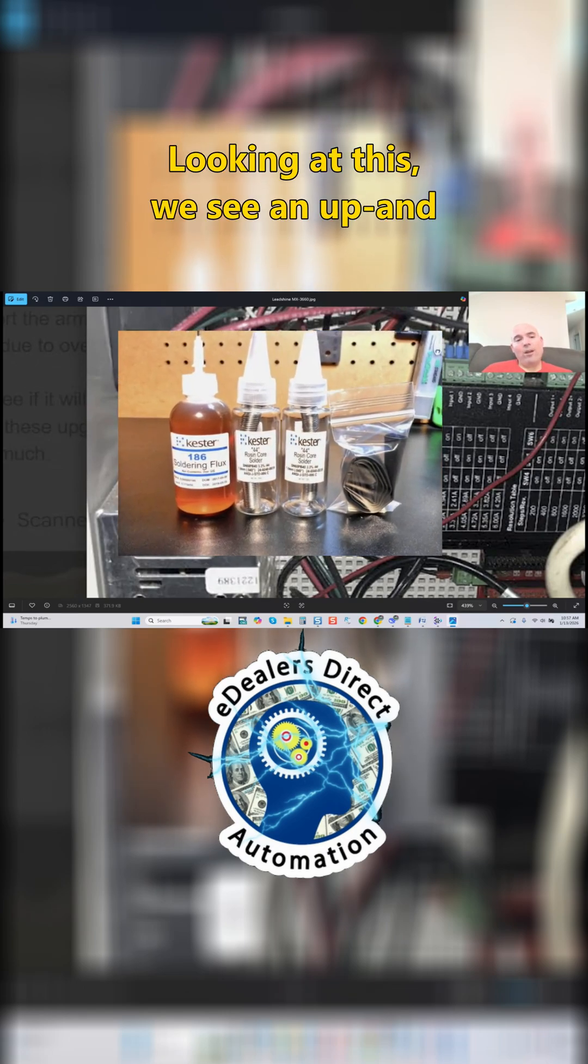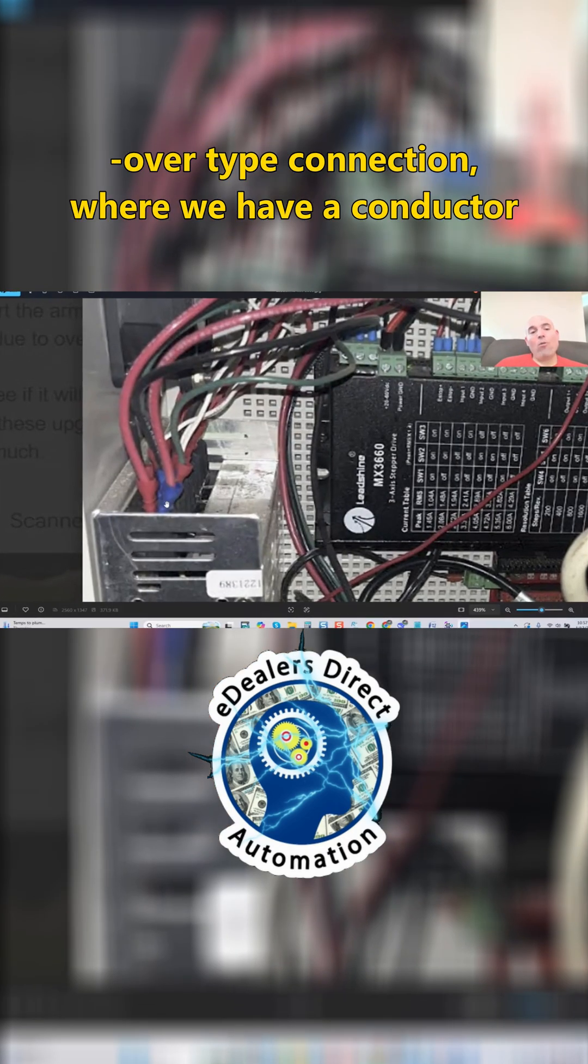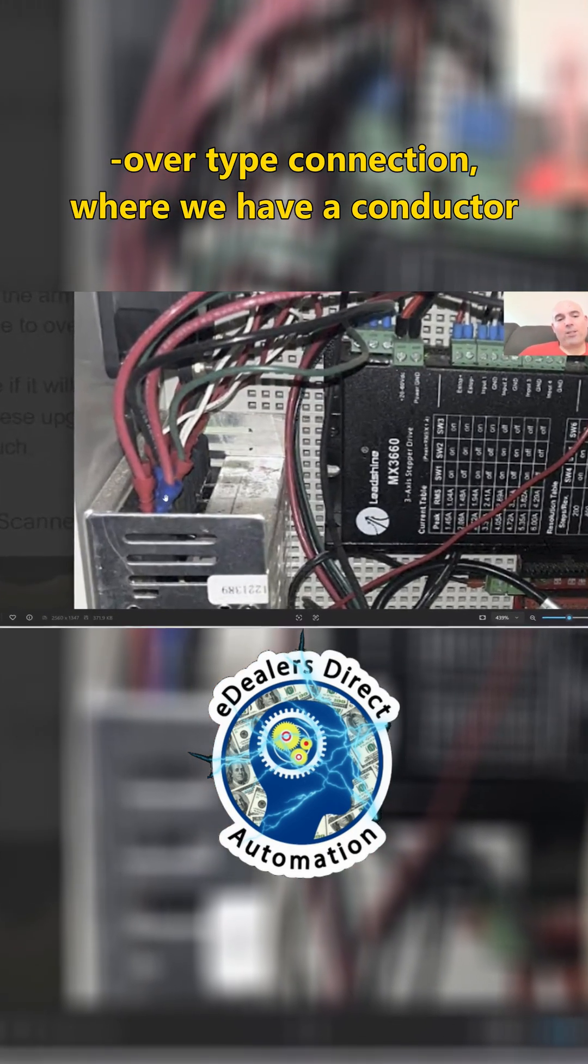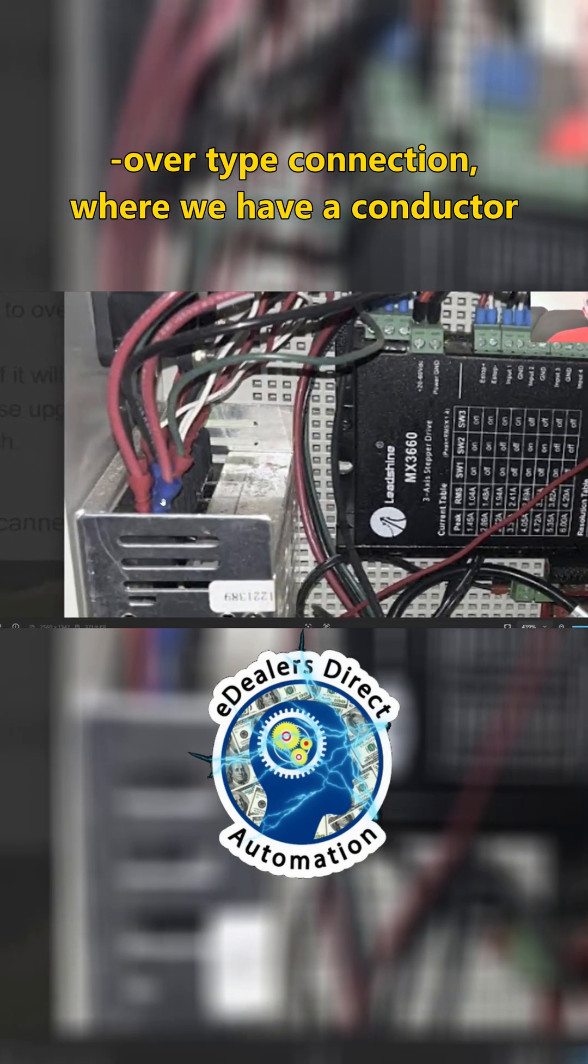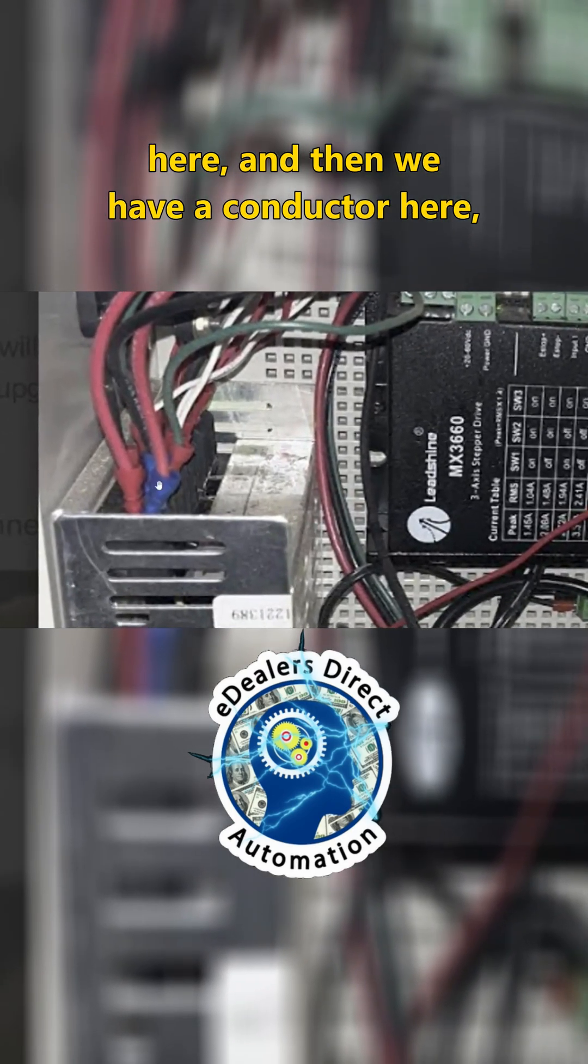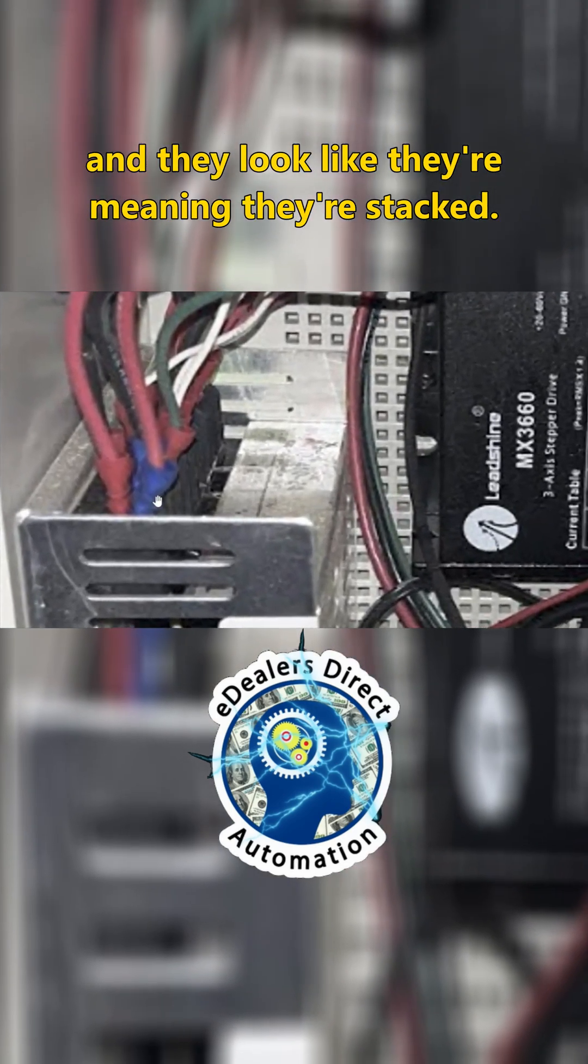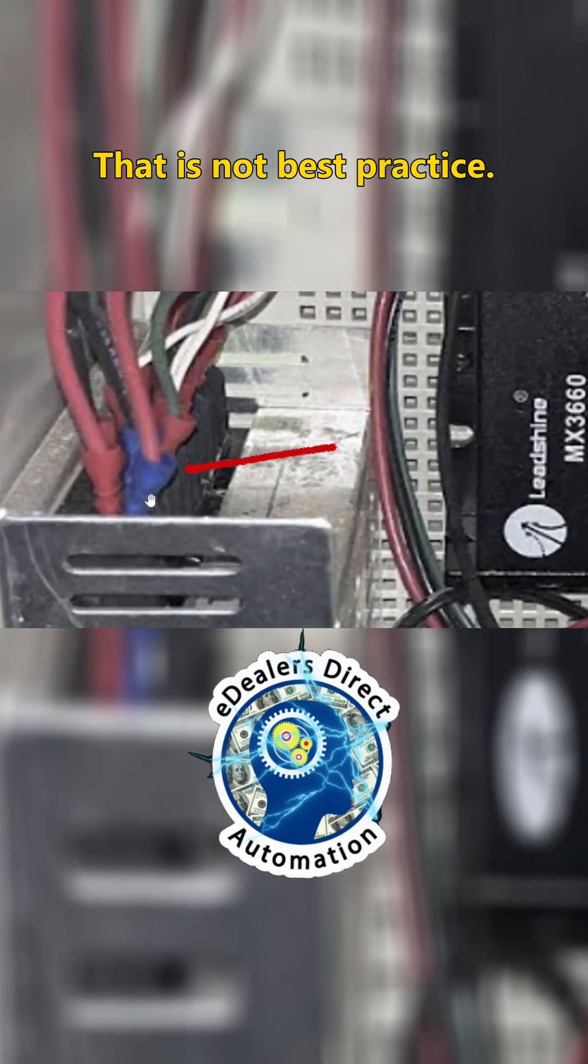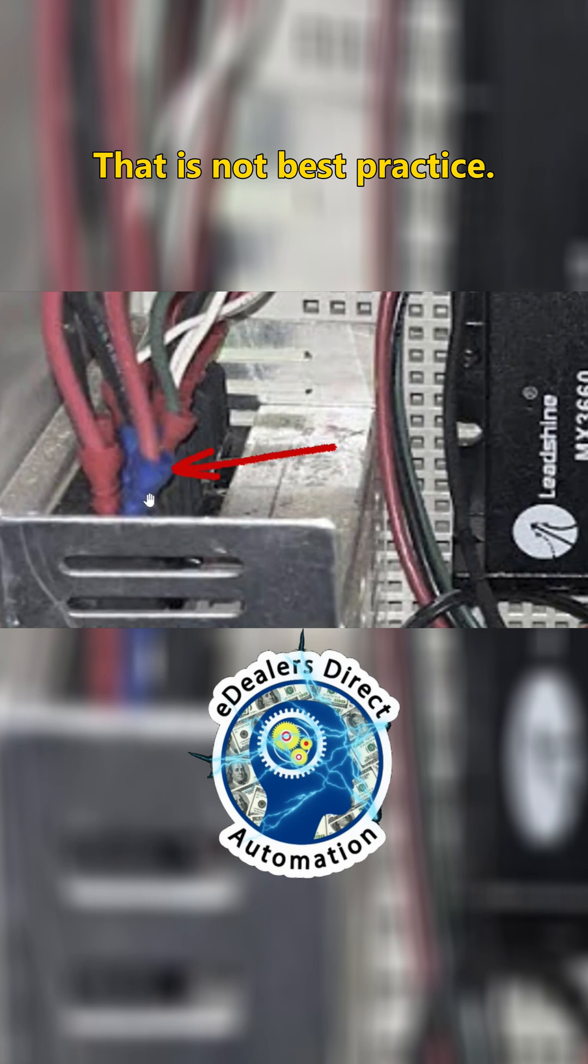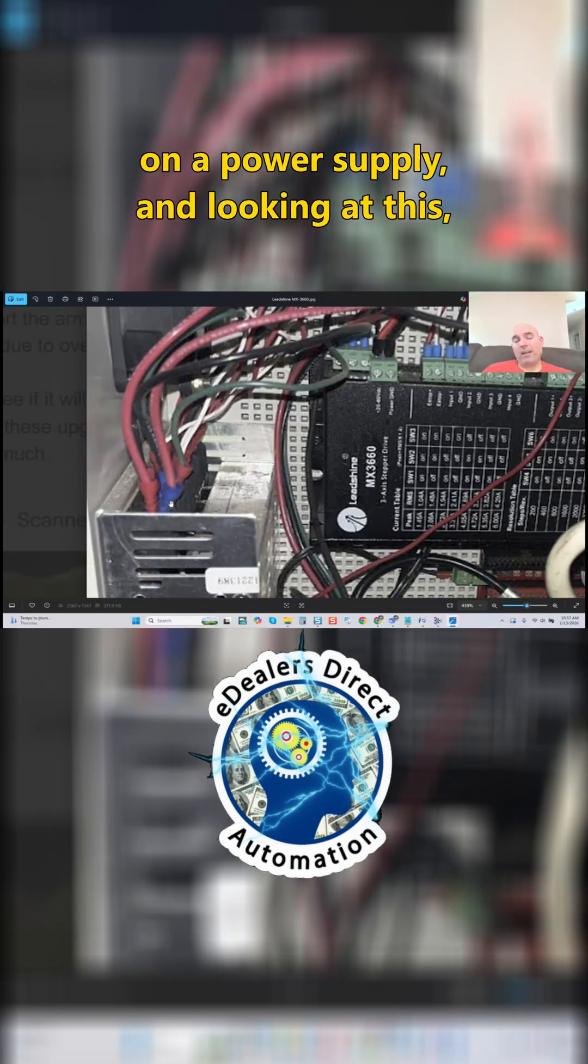Looking at this, we see an up-and-over-type connection where we have a conductor here and then a conductor here, and they look like they're piggybacked, meaning they're stacked. That is not best practice. That's not typically what you'd want to see on a power supply.